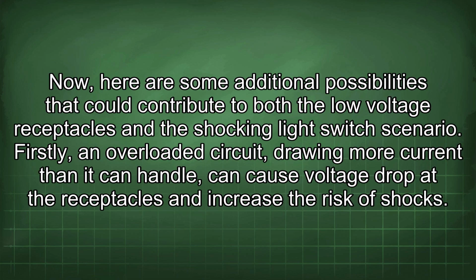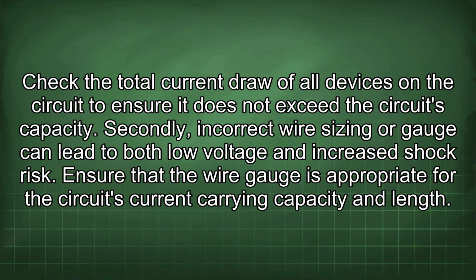Now, here are some additional possibilities that could contribute to both the low voltage receptacles and the shocking light switch scenario. Firstly, an overloaded circuit drawing more current than it can handle can cause voltage drop at the receptacles and increase the risk of shocks. Check the total current draw of all devices on the circuit to ensure it does not exceed the circuit's capacity. Secondly, incorrect wire sizing or gauge can lead to both low voltage and increased shock risk. Ensure that the wire gauge is appropriate for the circuit's current carrying capacity and length.